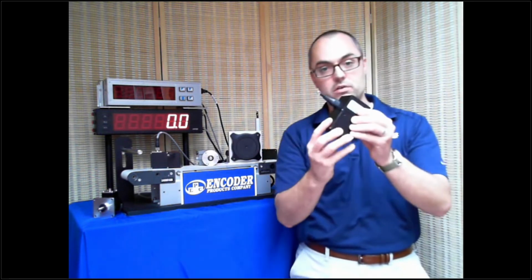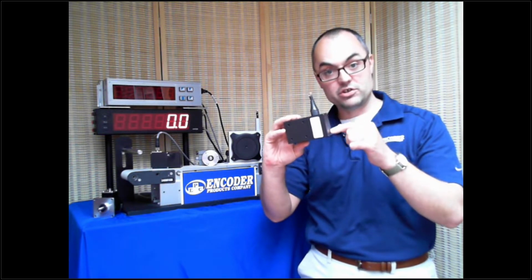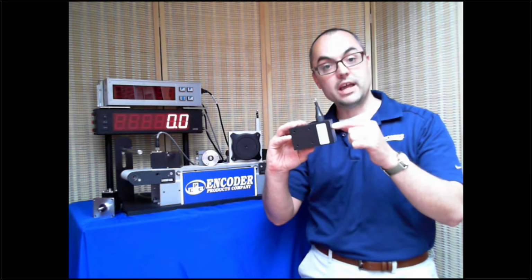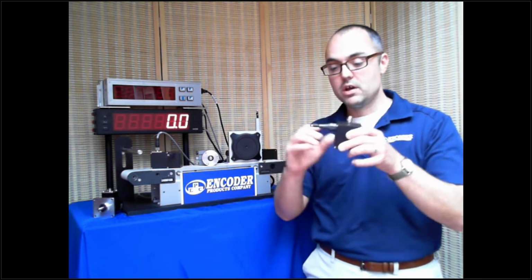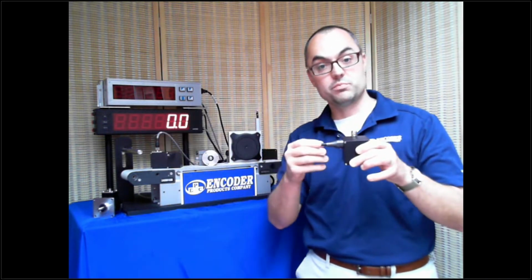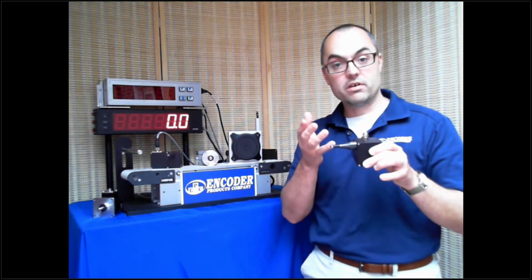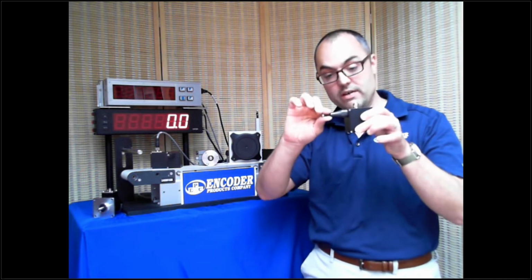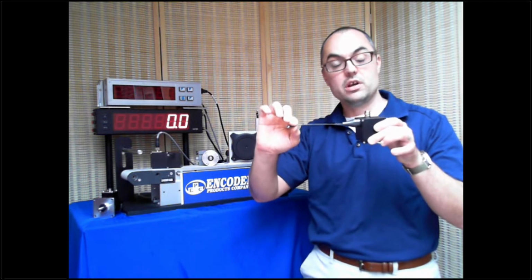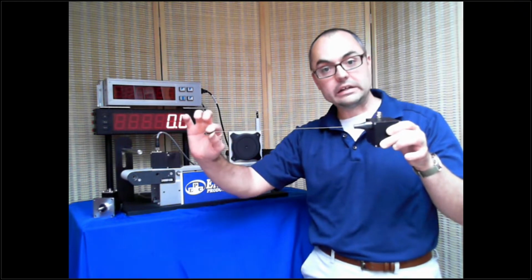So what a draw wire encoder does is we have here our very famous tried and true cube encoder attached to a drum, a precision machine drum with a 5-inch circumference with stainless steel cable around that drum. When I pull this cable, it rotates the encoder, in this case being incremental, creating those ticks, those pulses. So I'm able to count those ticks and figure out how far in or out my cable is. This encoder puts out 500 ticks or pulses per inch. So I've got a resolution here of 2/1000 of an inch of travel per tick mark. So I can very accurately measure the linear distance with this encoder.